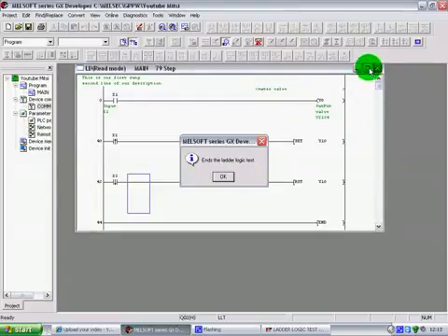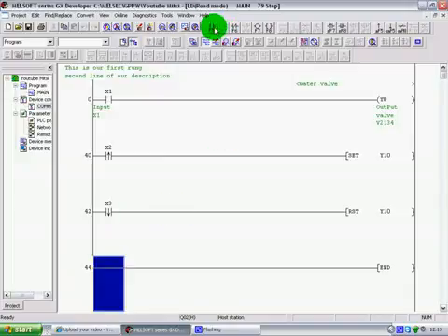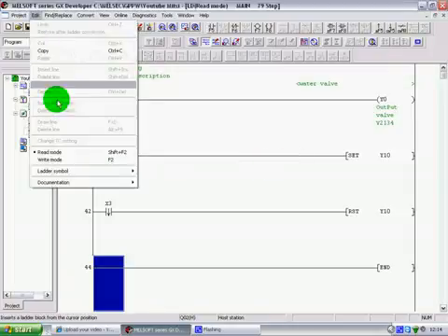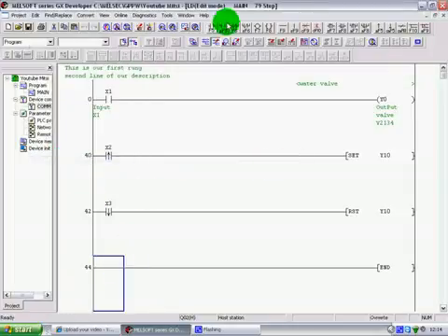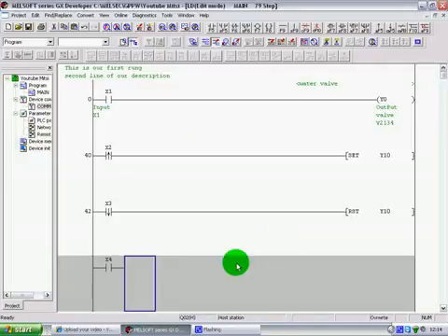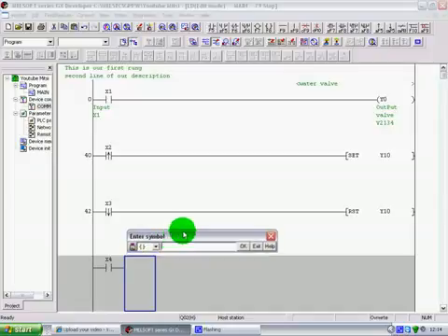Once this is reset, I will show you another command that you can use for pulses as well. Let's take an example, let's go for X4. Oh, we've gone back into read mode. Let's go back to write. Let's put X4, and we're going to put in F8 up here, and we're going to put in M11, but at this point we can put PLS, which is pulse M11.